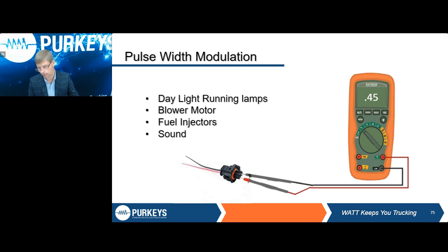So whether you're checking a blower motor, whatever, you use your percentage function, and it's going to tell you, hey, this is operating at 50%. 50% of the time it's on, 50% of the time it's off. It used to be, again, with a blower motor, you had three speeds. Now with pulse width, you can have basically infinite speeds based on how much the power's on versus off.